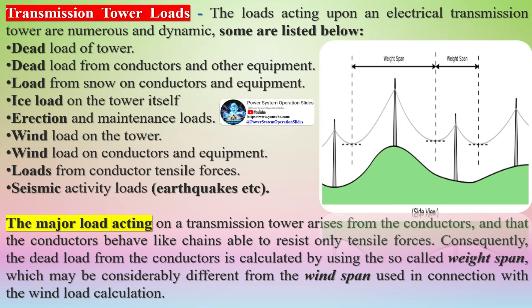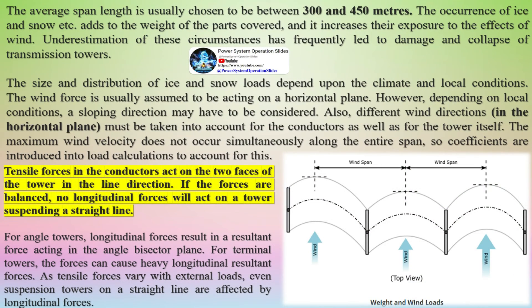The loads acting upon an electrical transmission tower are numerous and dynamic. These include: dead load of the tower; dead load from conductors and other equipment; load from snow on conductors and equipment; ice load on the tower itself; erection and maintenance loads; wind load on the tower; wind load on conductors and equipment; loads from conductor tensile forces; and seismic activity loads such as earthquakes.